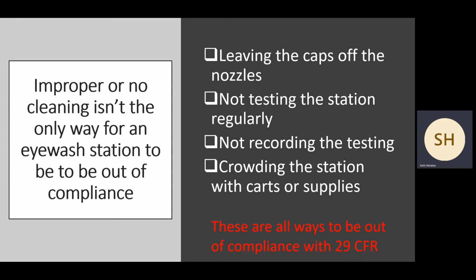Improper or no cleaning isn't the only way for eye wash stations to be out of compliance. Leaving the caps off the nozzles, that's usually stated in the manufacturer's IFU, so that's a problem. Not testing the station regularly, of course, not recording the testing. If you're doing it, the fact that you don't record it, it's just, it's too bad. You're spending the time to put this needed, necessary quality process in, and then you can't prove it, or crowding the station with carts and supplies. These are all ways to be out of compliance with 29 CFR.